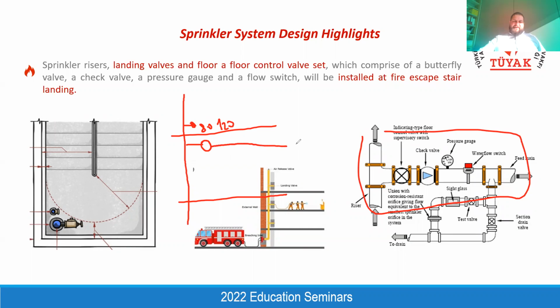And the system enters the floor by the staircase, but the valves are located nearest to the ceiling. That's why the location of the landing valves is really important. They should be checked whether they are encroaching the staircase circle. But for the gate valve group, you are more free. You have more flexibility because it's located nearest to the ceiling.